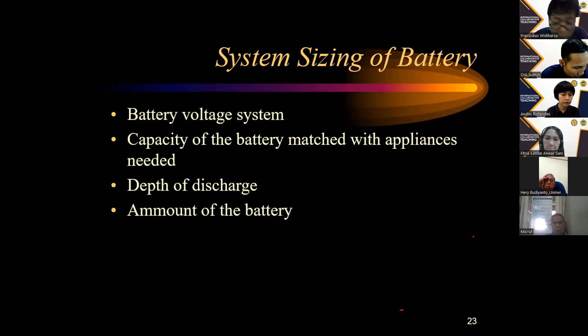Now we can calculate the size of the battery: compute watt-hours per day used by each appliance, then total watt-hours per day used by all appliances, then multiply the total per day by the depth of discharge factor. For example, a VRLA battery usually has 20% DOD, so we multiply by 5. But if we use a depth of discharge of 50%, we only need to multiply by 2.